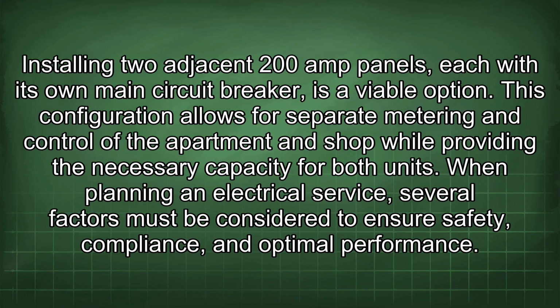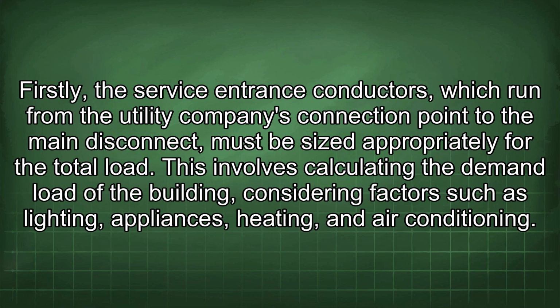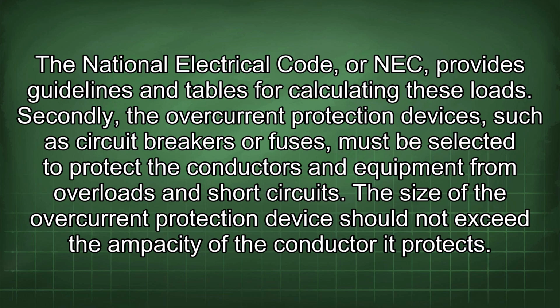When planning an electrical service, several factors must be considered to ensure safety, compliance, and optimal performance. Firstly, the service entrance conductors, which run from the utility company's connection point to the main disconnect, must be sized appropriately for the total load. This involves calculating the demand load of the building, considering factors such as lighting, appliances, heating, and air conditioning. The National Electrical Code, or NEC, provides guidelines and tables for calculating these loads.